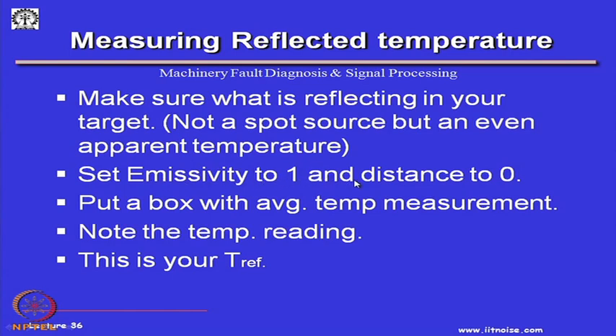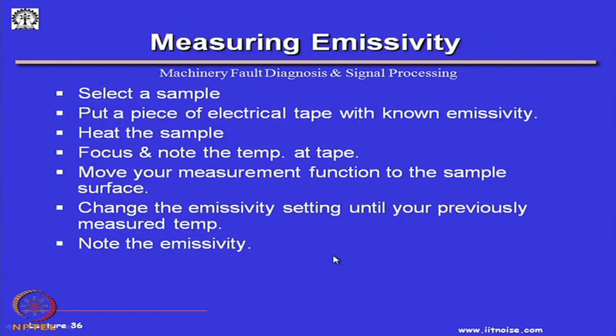Set emissivity to 1, okay, and then you can find out the average temperature. So one way to measure emissivity is: select a sample, put a piece of electrical tape with known emissivity, heat the sample, focus and note the temperature at the tape, move your measurement function to the sample surface, change the emissivity setting until you get the previous temperature. And that is what I told you in the method. So you can change the emissivity till you get the right temperature. That is what people follow in the field.